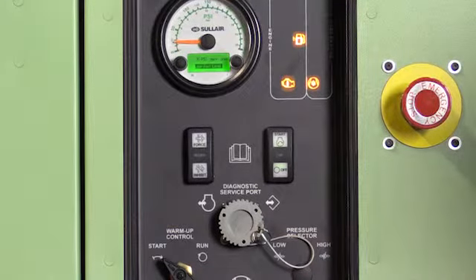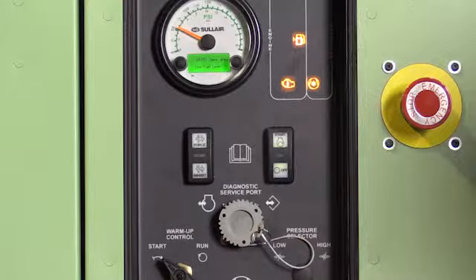The start-run valve in the start position is holding the inlet closed, basically putting this machine in a forced unloaded state. This keeps the sump pressures down to a minimum, just enough to have oil flow so that the engine can start freely and keep torsional vibration down.